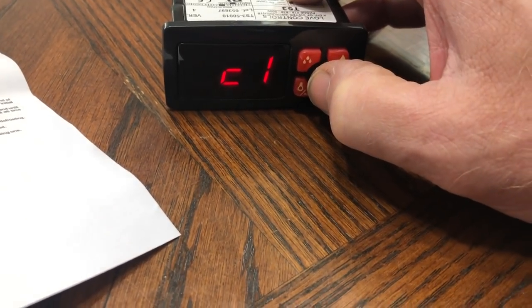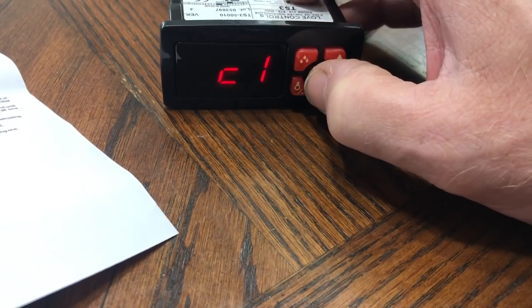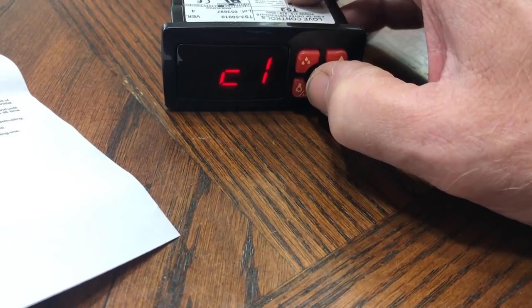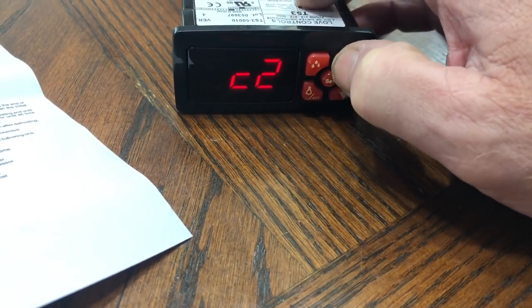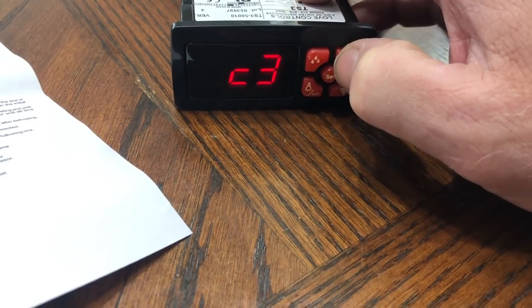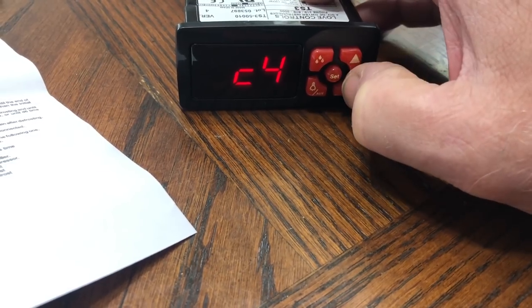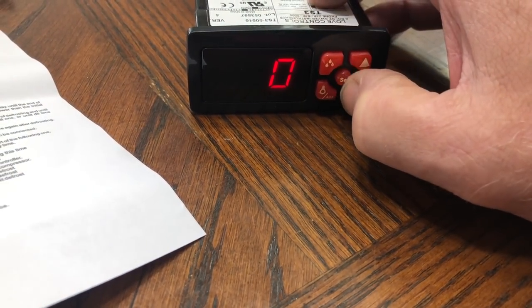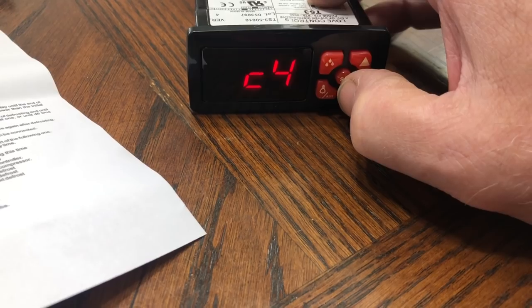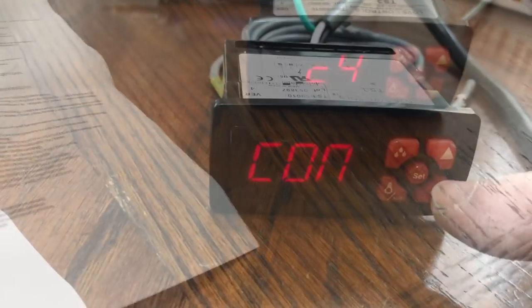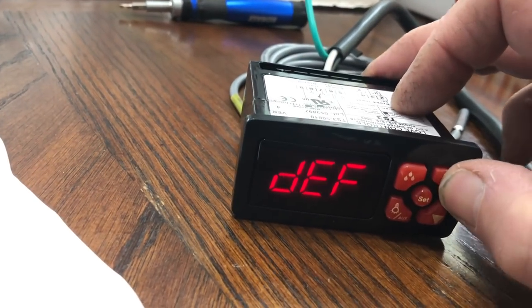Minimum compressor stoppage time. You can go in minutes. Factory set point is one. I'm going to leave it there. I'll come down to C1. Continuous cycle time. Then you can go to C2, C3, C4, and so forth. Set and down at the same time. It takes you back to the sub parameters.